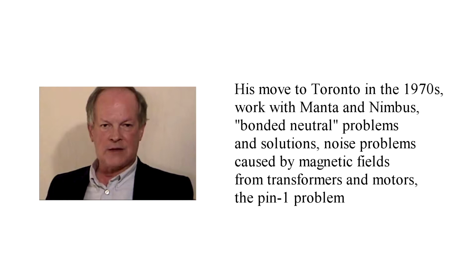And older buildings, you just go in with the understanding that you're going to have neutral bonds coming out of your ears. It turns out when you're wiring a building and you have a breaker panel at the service entrance, there is a screw in the neutral bar which bonds the neutral bar to the box, and then that's what you send to your ground rod. That's the building ground, that's what it's called.